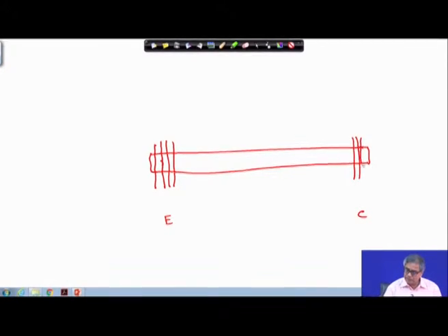heat pipes can transfer heat from one gas to another gas, let us say from a hot gas to a cold gas. So, outside we can see that gas is there, or basically the heat pipe can be part of a gas to gas heat exchanger. The gas side heat transfer coefficient is very small. So, to improve it there could be fins like this, these are radial fins.